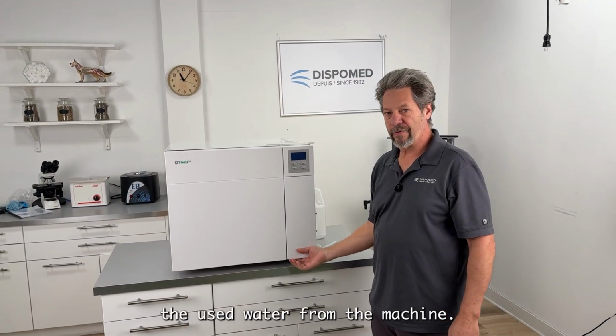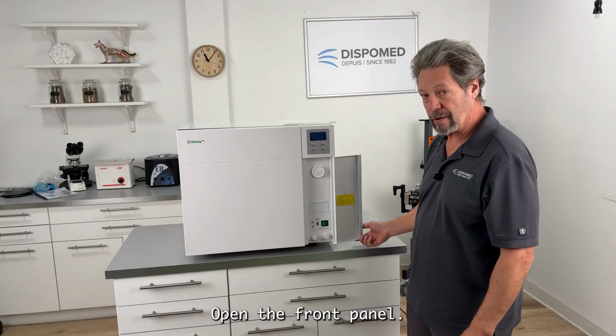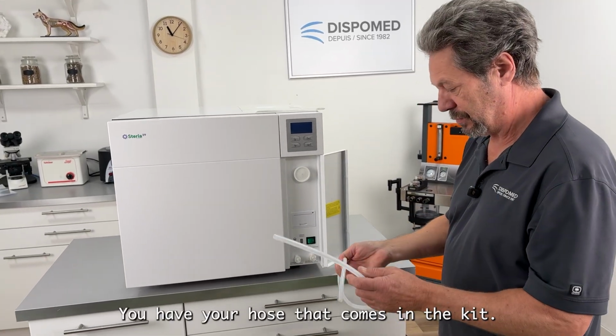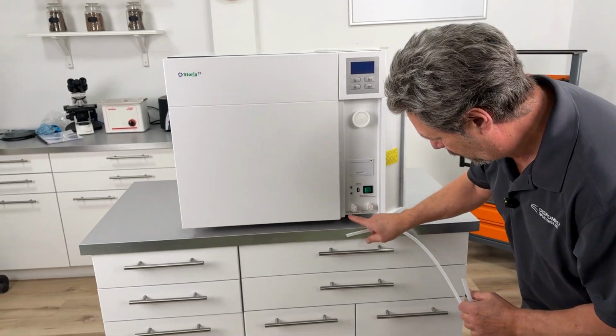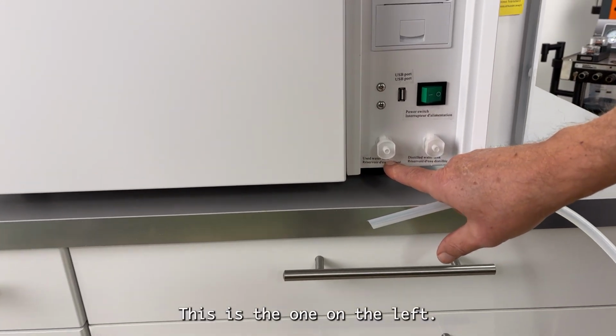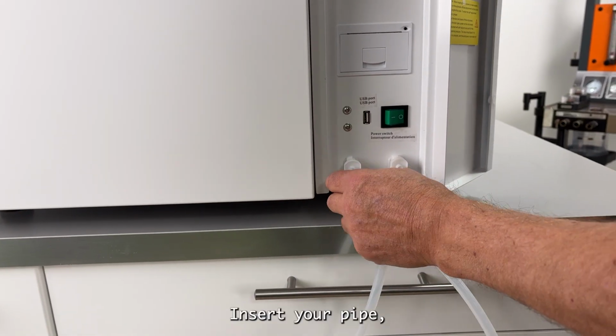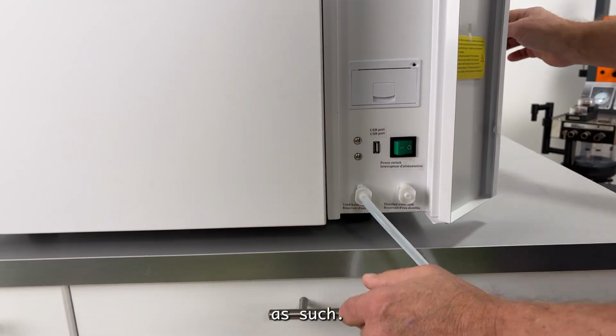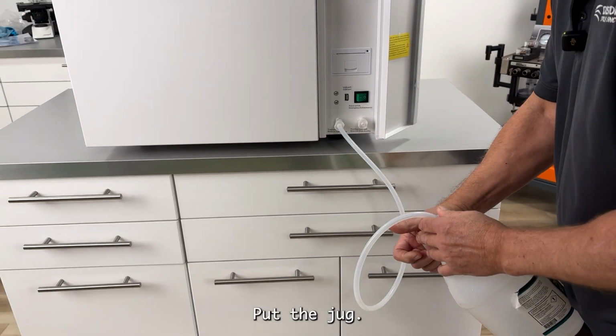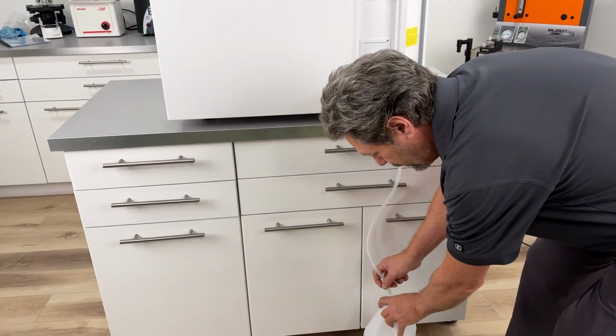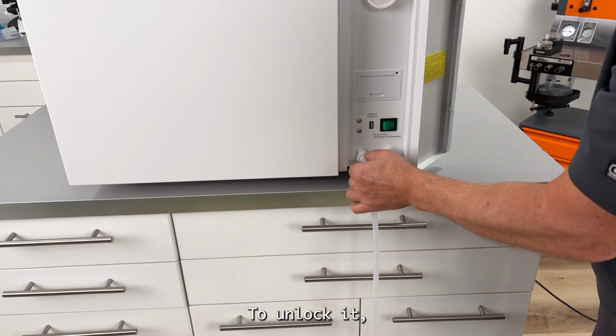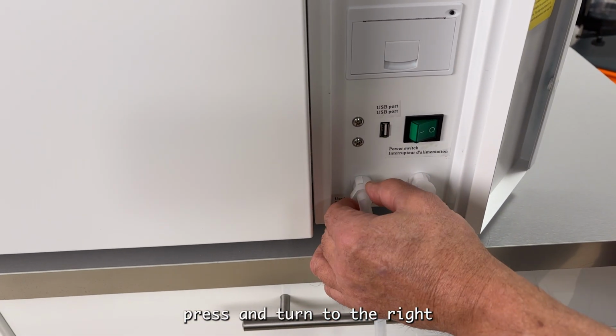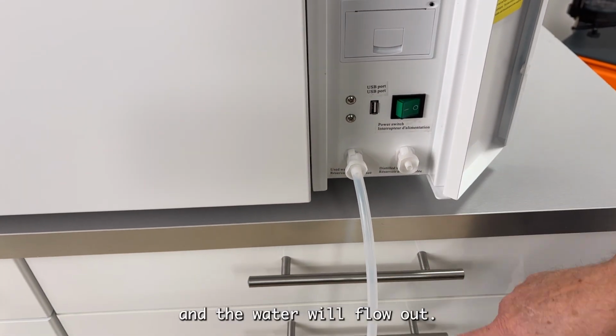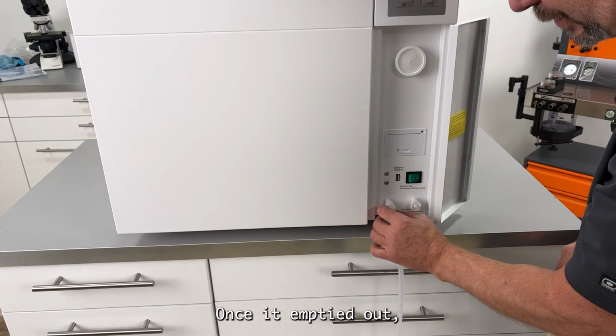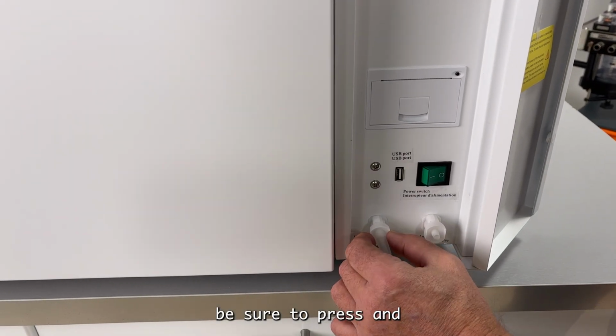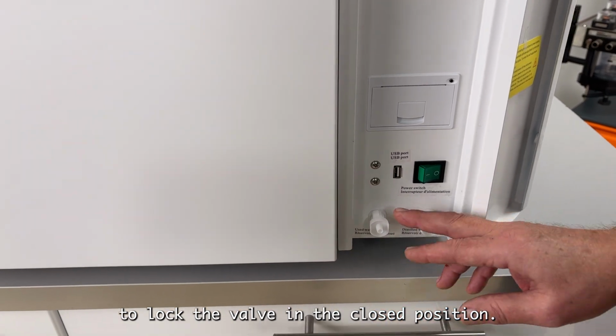To empty out the used water from the machine, open the front panel. You have your hose that comes in the kit. The used water is the one on the left. Insert your pipe as such with a jug. To unlock it, press and turn to the right and the water will flow out. Once it's emptied out, be sure to press, turn to the left to lock the valve in the closed position.